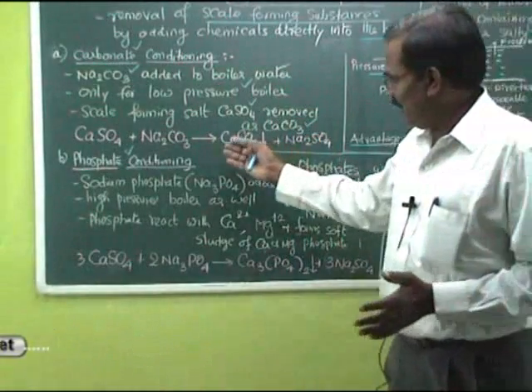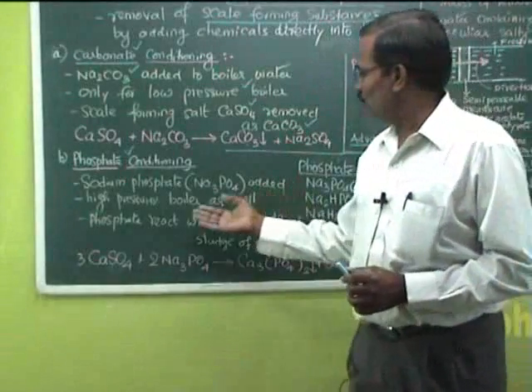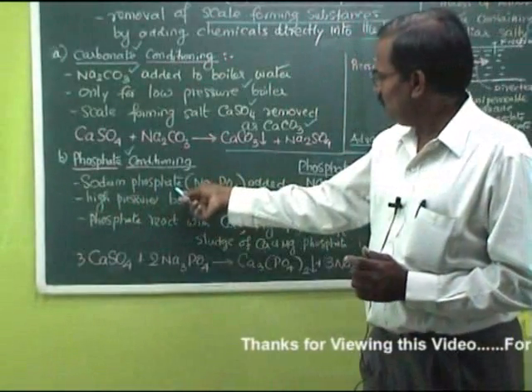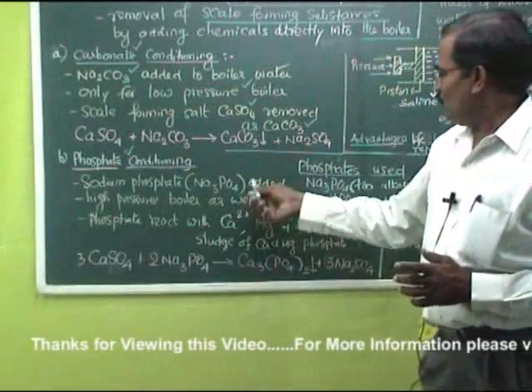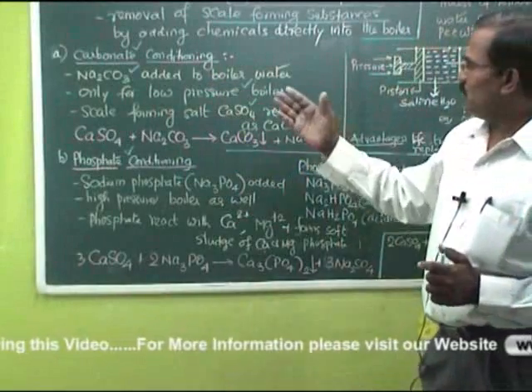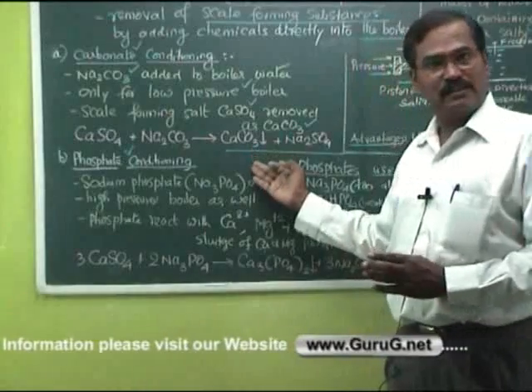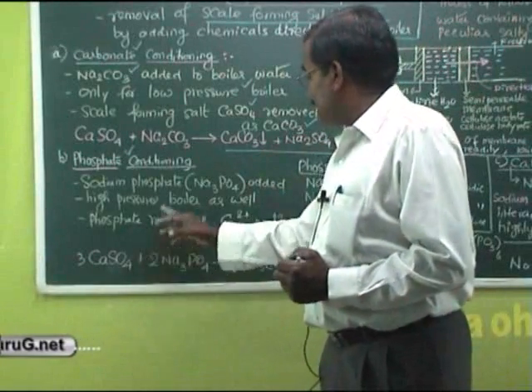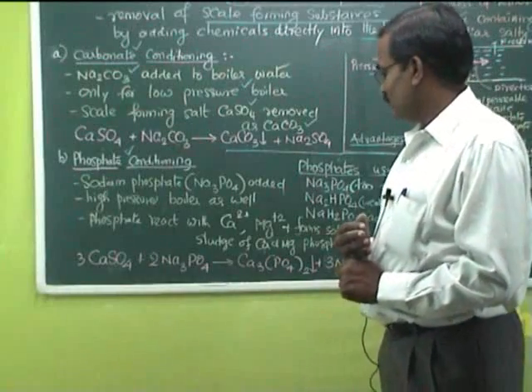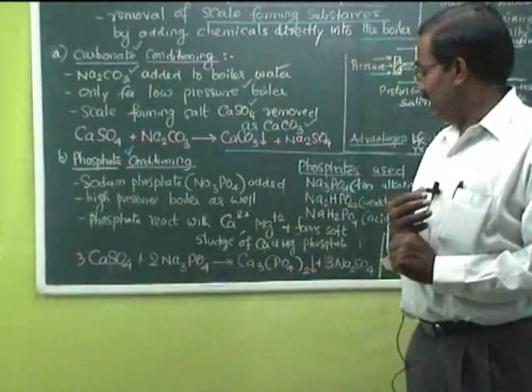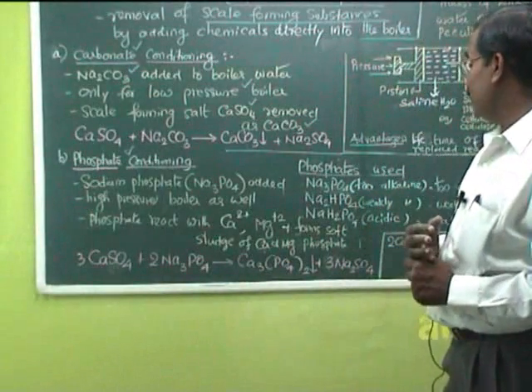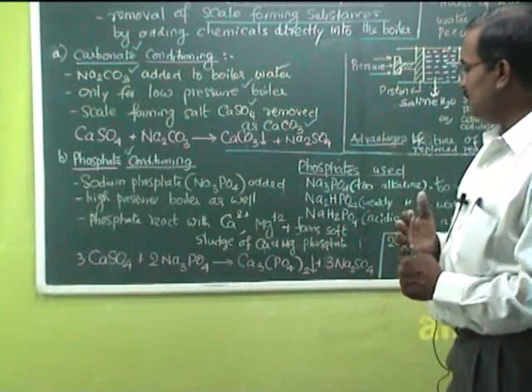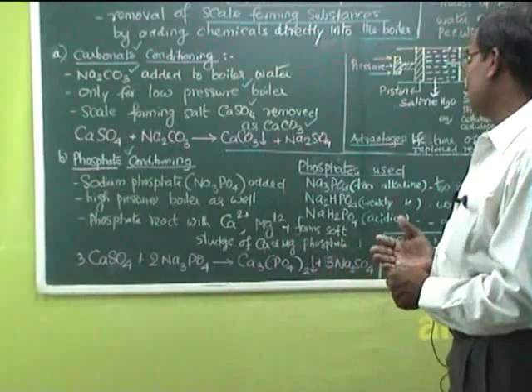The second method is phosphate conditioning. It is applicable for both low-pressure as well as high-pressure boilers. We are adding sodium phosphate in the place of sodium carbonate. The calcium sulfate scale-forming compound present in the boiler water reacts with sodium phosphate, forming water-insoluble calcium phosphate sludge. The sludge can be readily removed, so the hardness-causing calcium sulfate is removed as calcium phosphate sludge.